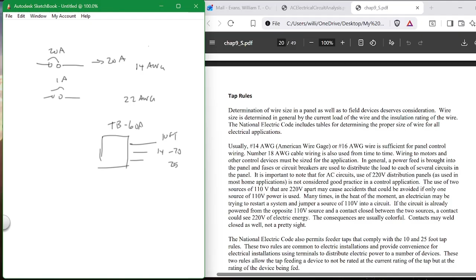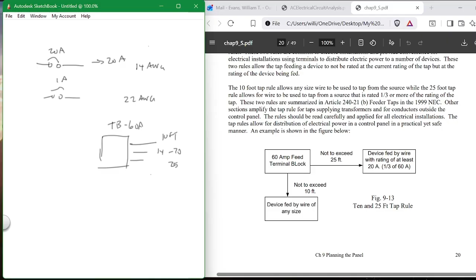Okay? Now, what is the rule here? It's this called this tap rule. Okay? So if I have a block that's feeding wires, I do not have to provide a circuit breaker for every wire in a control panel if I don't exceed these two rules. 10 foot for any gauge wire, 25 foot for a wire that is rated at a third of the ampacity of the terminal block. Probably never thought of that before, but when you're getting into building of panels, this is a big plus because you don't have to provide circuit breakers for all these little wires, all these little circuits, okay?